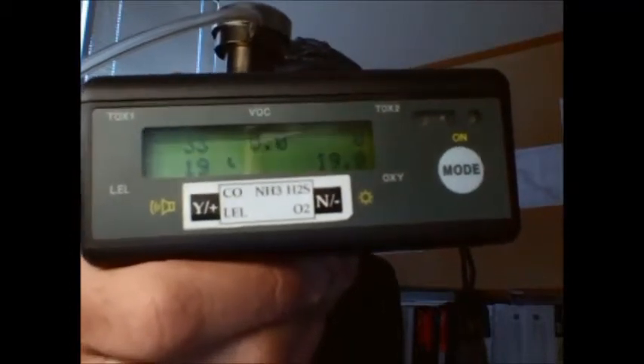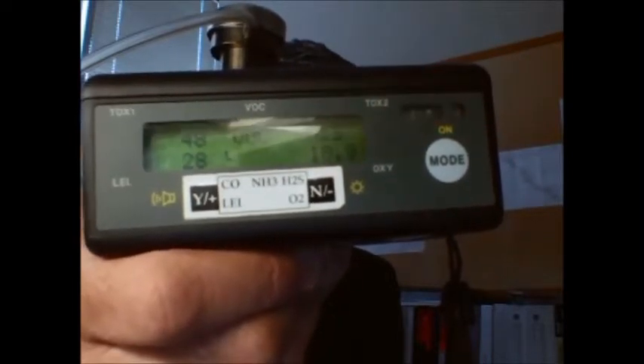Now, before I do that, I just want to reiterate that we're not going to do a calibration here. This is strictly a bump test, and what that means is we're just going to bump the detector to see if the alarms work. So here we go. I'll put this right here. I'll plug that right in, and there we go. Now you can see there's a low. So you see the CO, the LEL, and the oxygen all coming in with the alarms, and those are the 3 that we're testing. So you do not want to keep applying gas. You just want to apply enough gas to bring in the alarms.